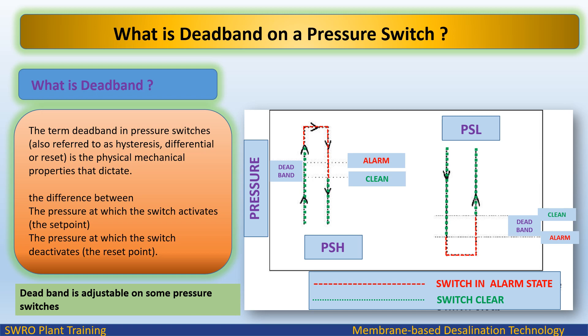What is dead band on a pressure switch? The term dead band in pressure switches — also referred to as hysteresis, differential, or reset — is the physical mechanical property that dictates the difference between the pressure at which the switch activates (the set point) and the pressure at which the switch deactivates (the reset point). Dead band is adjustable on some pressure switches.